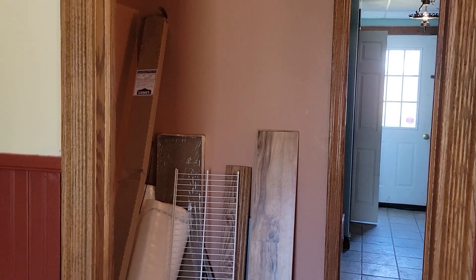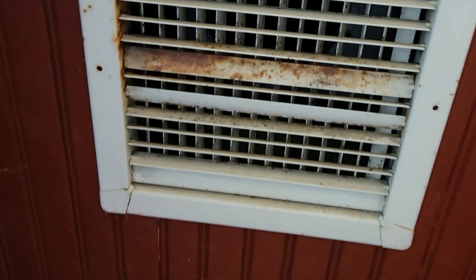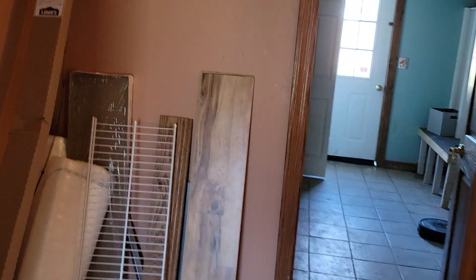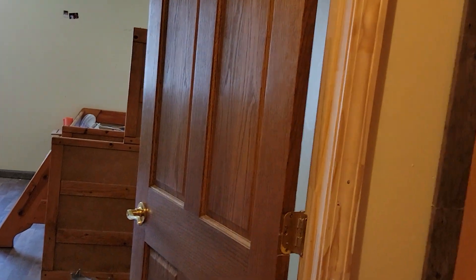I notice this return right here — this vent is really dirty, so I'm thinking there either isn't a filter or it hasn't been changed, which tells me the maintenance of the home isn't very good. The rust on this vent: all that water down in the basement is causing a massive amount of humidity coming through the HVAC system and in turn coming through the vents, causing the rust. So you have a lot of humidity coming through.